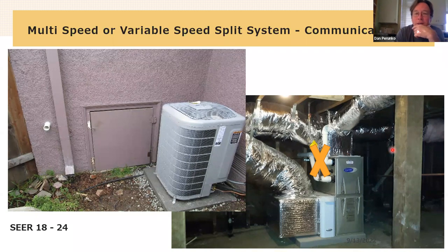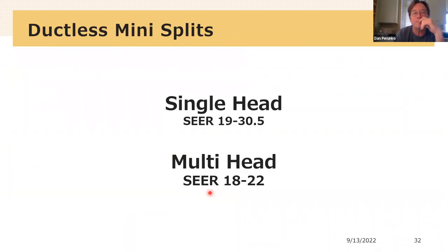So what I want you to get out of this is that the communicating systems can look like the legacy systems, and that the sort of better communicating systems tend to be the mini split style machines, which you'll see soon. The highest efficiency machines out there are ductless mini splits, right? So no duct system of any kind. And you can get them in single head versions where there's one outside unit and one inside unit, or you can get them in multi-head systems where there's one outside unit and as many as like six or seven inside units.